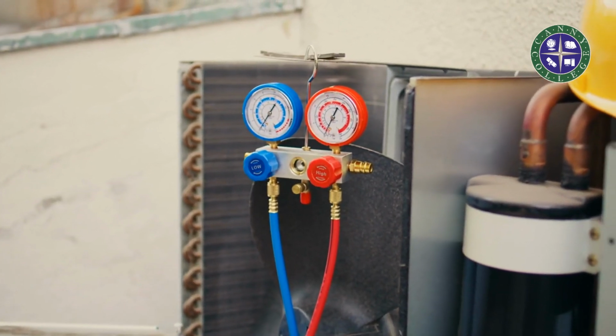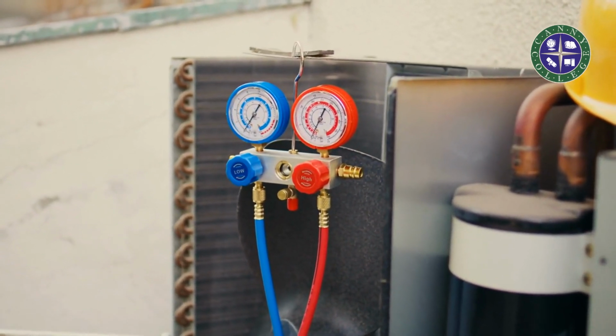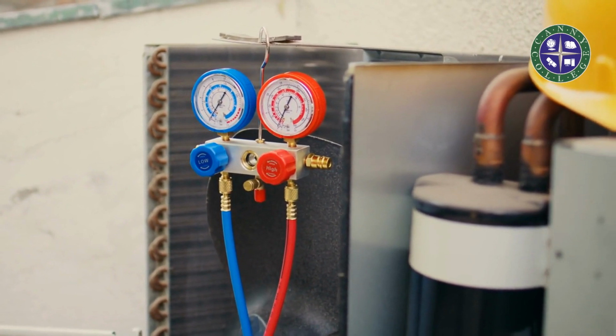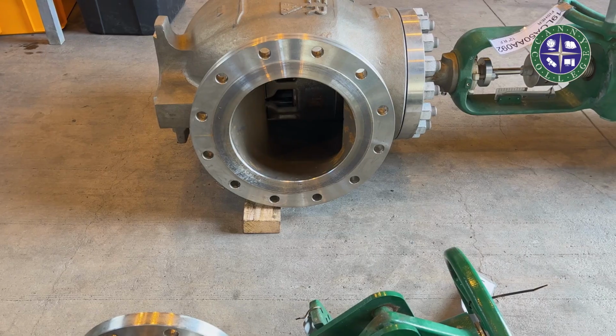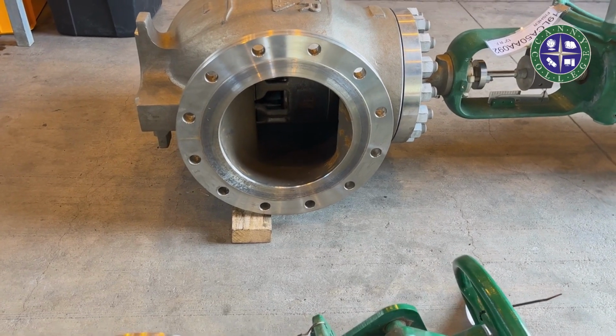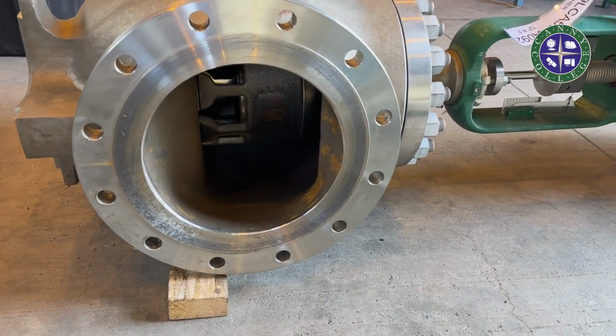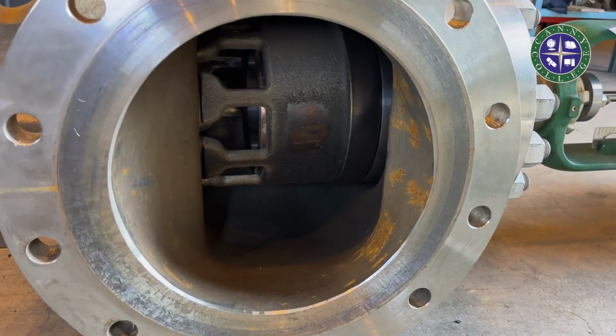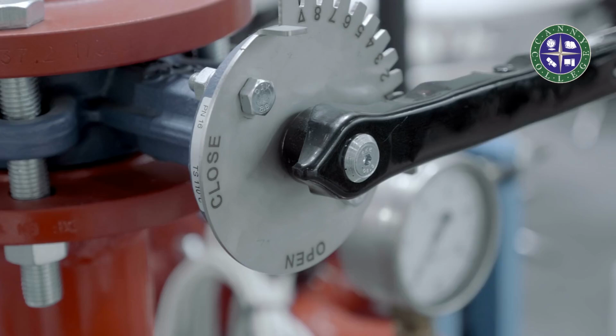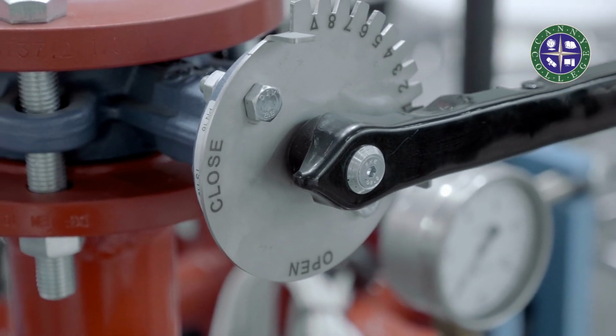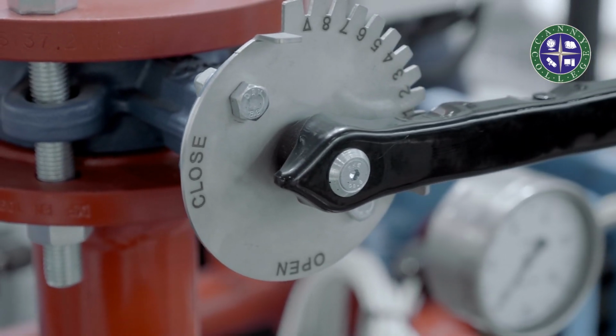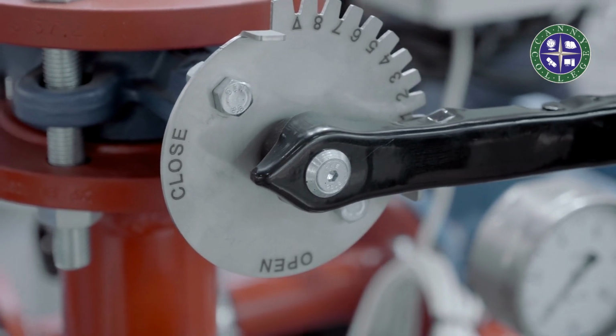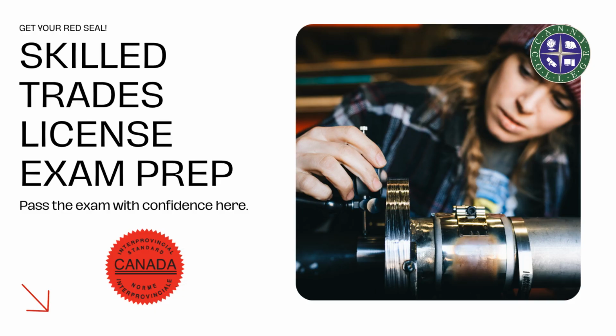1. When performing a manual pump down procedure, the king valve needs to be adjusted to stop the flow of refrigerant to the system. Turning the stem of the king valve clockwise to the front seat position will close off the valve completely, preventing any refrigerant flow through the system. 2. The front seat of the valve refers to the fully closed position where the valve is fully seated, blocking the flow of refrigerant. Turning the stem of the king valve clockwise to the front seat ensures a tight seal and effectively shuts off the refrigerant flow.